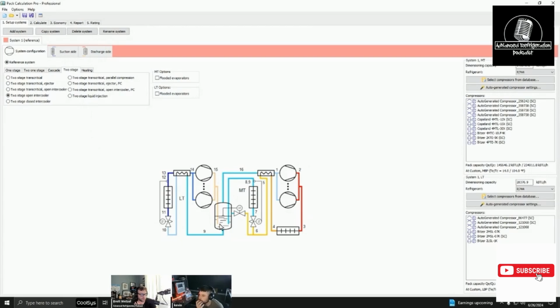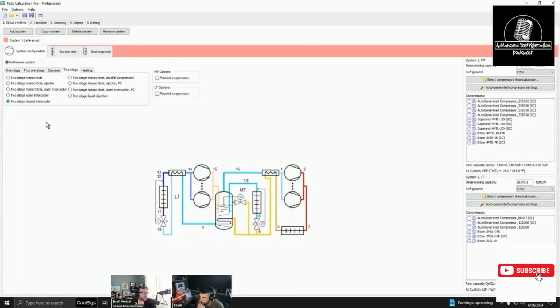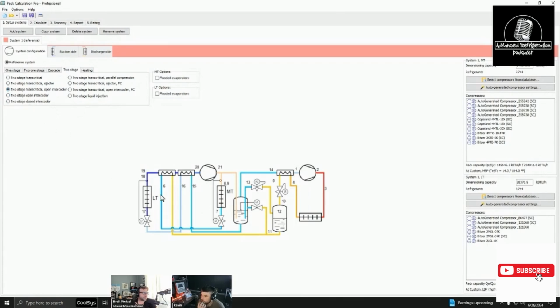So you're shooting literally discharge gas from the low temp. That's what that trainer does, the Emerson one, right? Yep. And then there's your 2-stage where it has a closed intercooler and I guess an open intercooler, so it's essentially doing both, right? And then you have 2-stage transcritical open. Holy crap, yeah, so this basically encompasses almost everything we're doing.